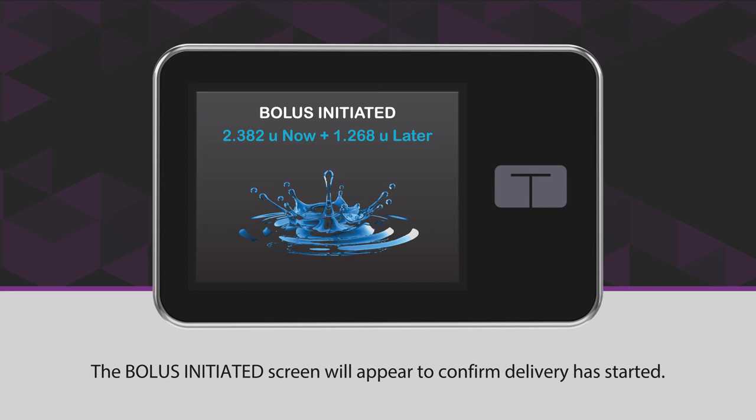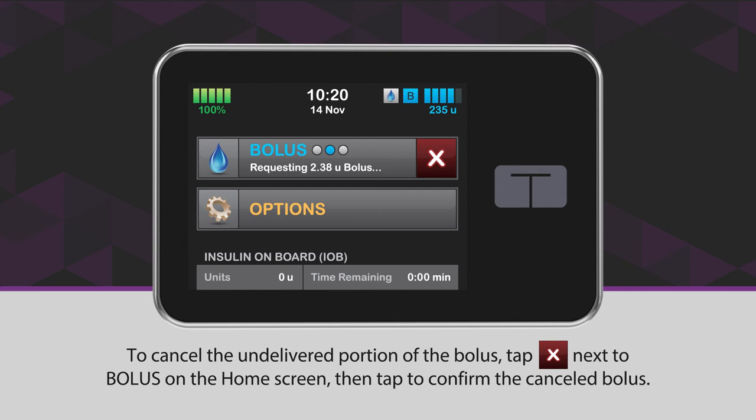The bolus initiated screen will appear to confirm delivery has started. To cancel the undelivered portion of the bolus, tap the white X icon in the red square next to Bolus on the home screen, then tap to confirm the canceled bolus.